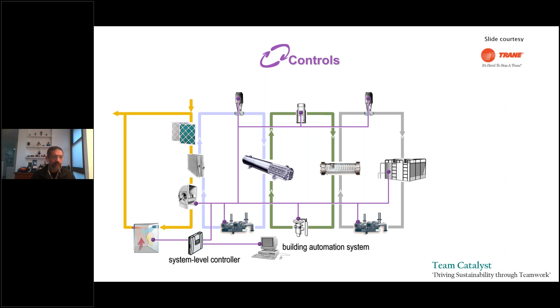So here's my representation of exactly what I just showed you inside this energy simulation program. Here is a zone where I am going to be providing comfort. That comfort is going to be provided by this air handling unit, which has got a fan to supply the air in and another fan that pulls the return air back. There's a cooling coil there that makes this air cold. There's a controller that decides the control strategy for this loop. This cooling coil will be having chilled water pumped through from a chiller. The chiller will have a pump. It will have a controller which decides how the chiller is going to operate to chill the water.